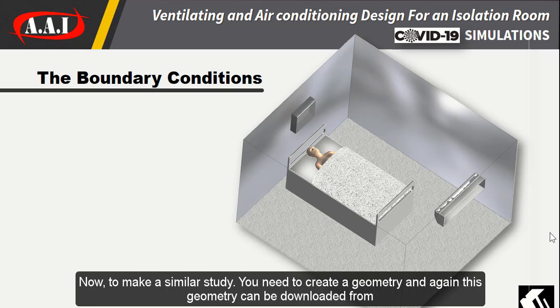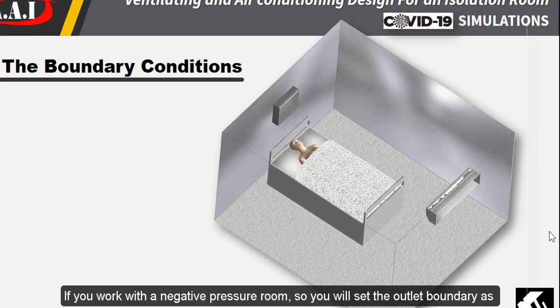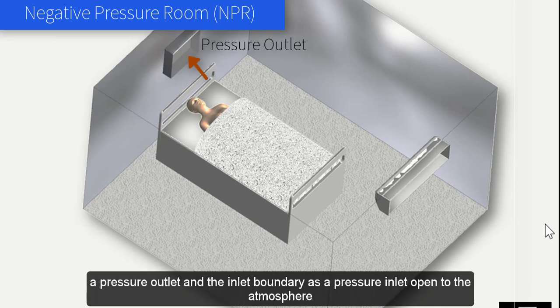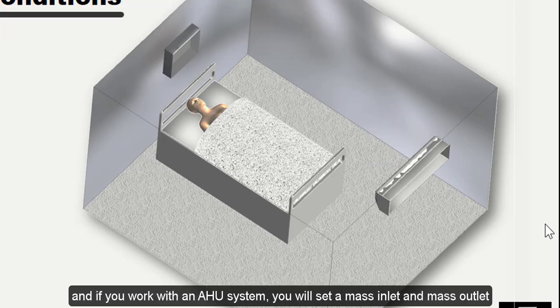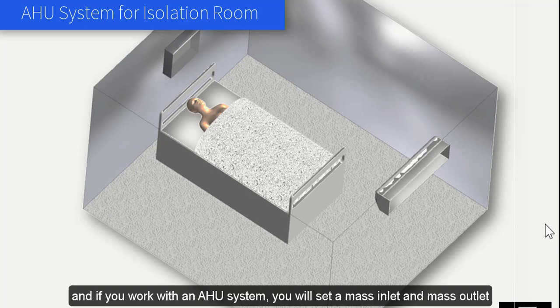To make a similar study, you need to create a geometry — which can be downloaded from the link in the description of this video — and you need to set boundary conditions. If you work with a negative pressure room, you will set the outlet boundary as a pressure outlet and the inlet boundary as a pressure inlet open to the atmosphere. If you work with an AHU system, you will set a mass inlet and mass outlet.